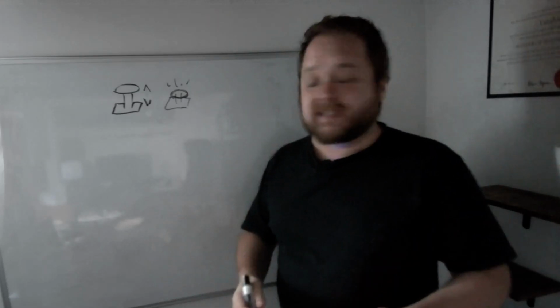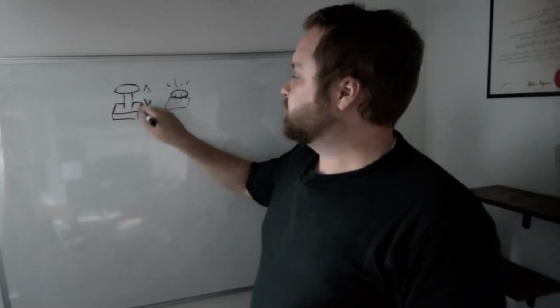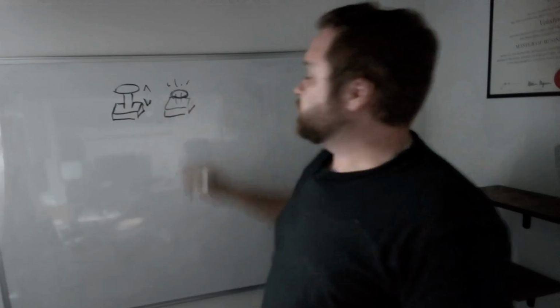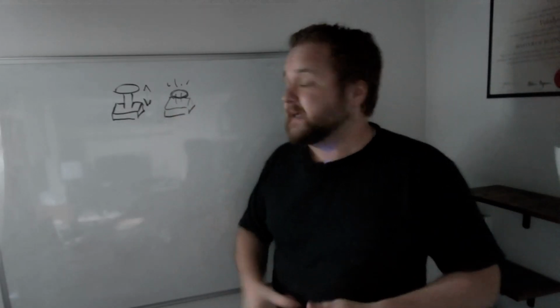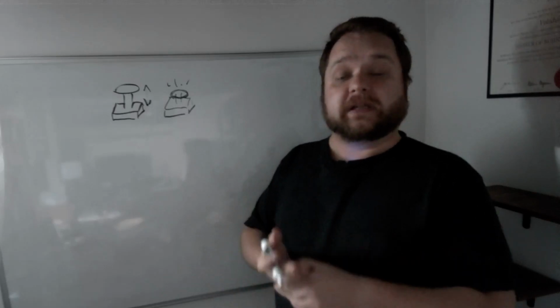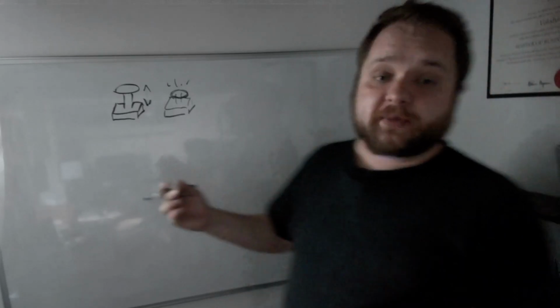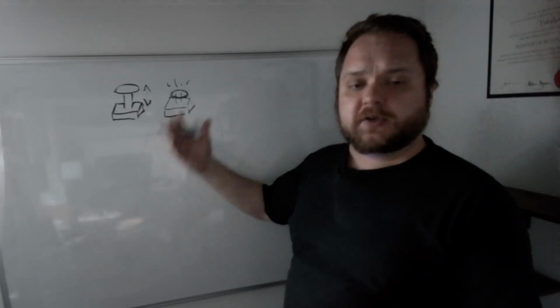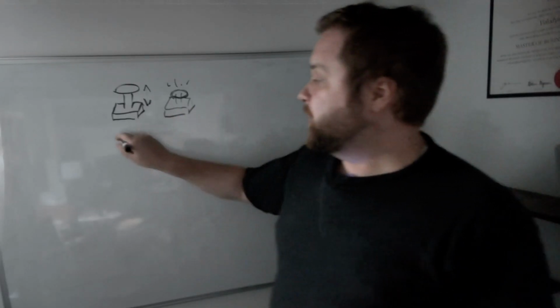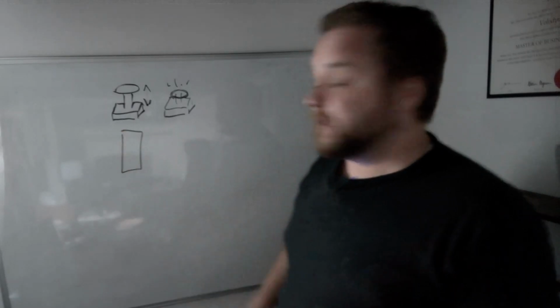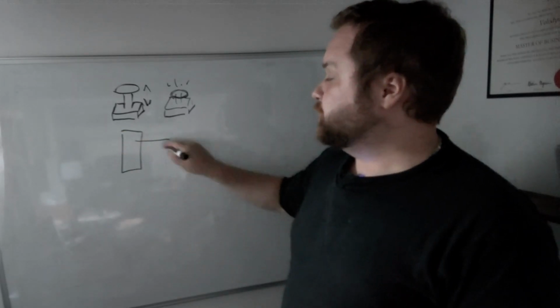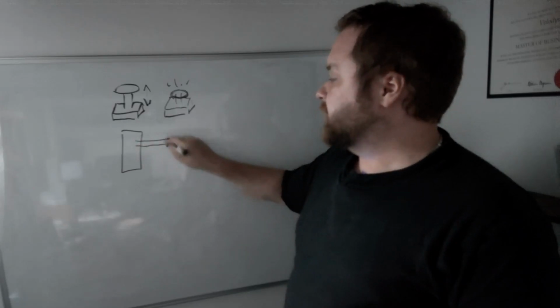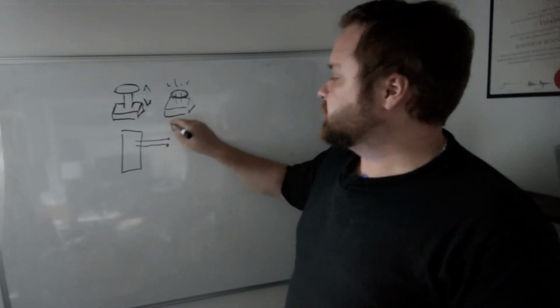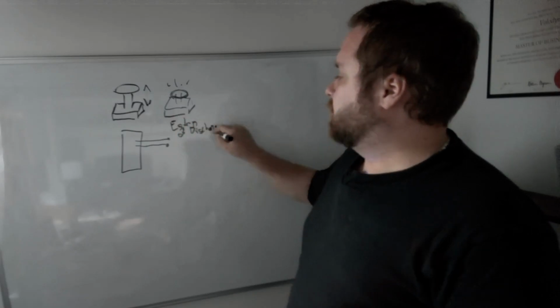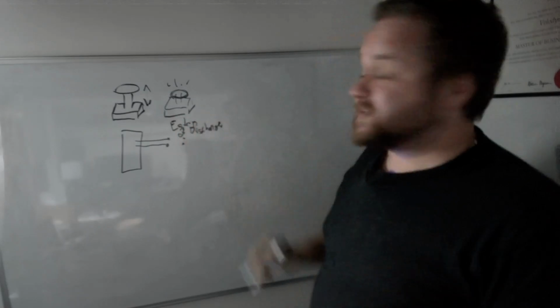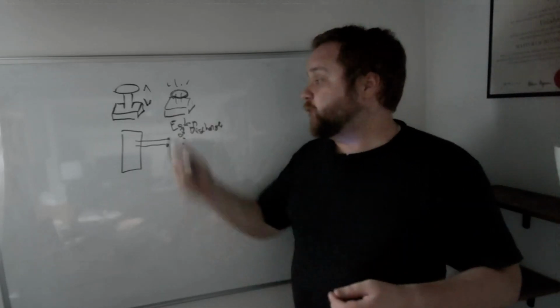So the first step, obviously, is to check the physical devices, right? And this is going to be some kind of a box where the wires come in, but you want to double check that none of those are pressed. The second step that you should be looking at is your electrical schematics. So your electrical schematics are going to contain the information that I basically drew very rapidly on the whiteboard, but you should have a set of safety relays that will be connected to usually e-stops and obviously other devices, but it will tell you, so this is going to be e-stop, e-stop at discharge. So you should probably be looking at that specific e-stop if you're looking to understand whether or not it is correct.